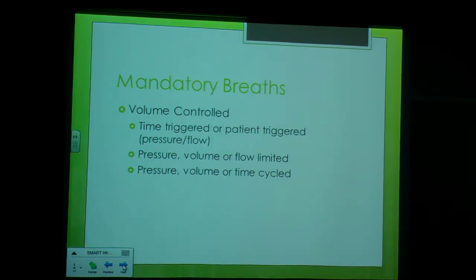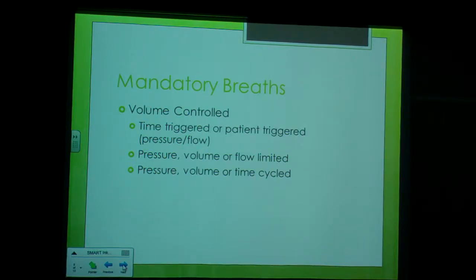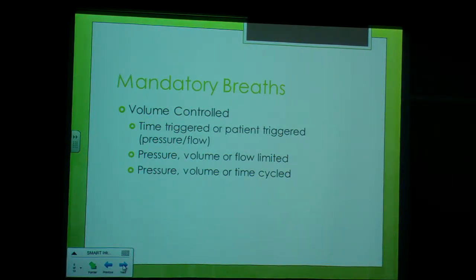With the mandatory breaths in the volume control mode, they are triggered by time or patient effort. When patient-triggered, it is triggered by pressure or flow. The breath is limited by pressure, volume, or flow, and it's cycled by pressure, volume, or time.